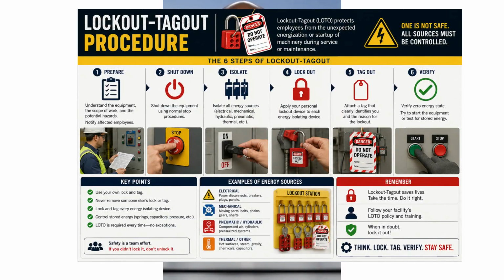One thing that's easy to forget mid troubleshoot: a PLC does not replace lockout tagout. Even sitting in stop mode, always isolate electrical energy before you touch any wiring. Before you replace any component, run through these 5 questions. Is power available? Is the input actually reaching the PLC? Is the PLC making the right decision? Is the output energized? Is the field device itself actually working? Follow the signal, not your assumptions.